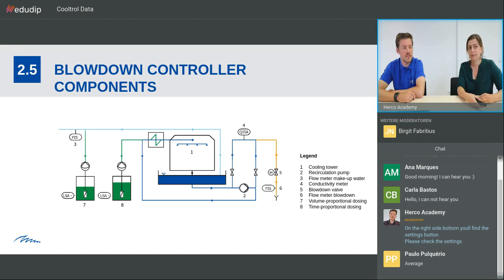This is the biocide. This is not controlled by the makeup water flow because even if the cooling tower doesn't use makeup water or is in standby right now, is not being used, we still need to dose biocide in order to avoid biological growth. This is dosed directly in the recirculation line, and it is controlled with a timer.